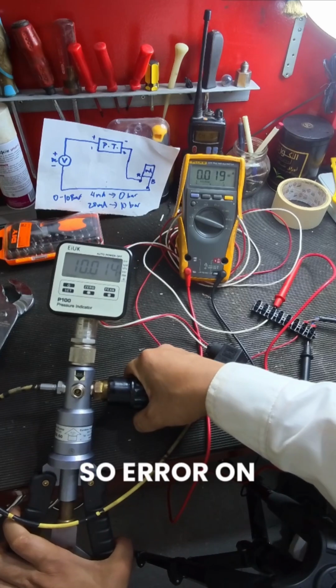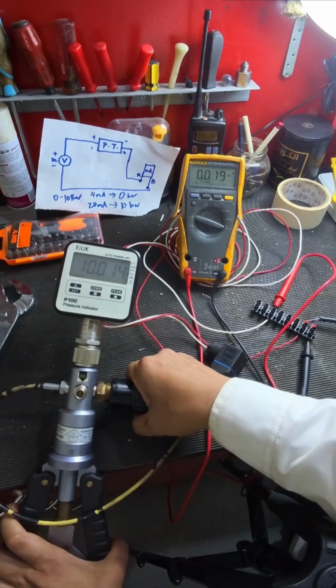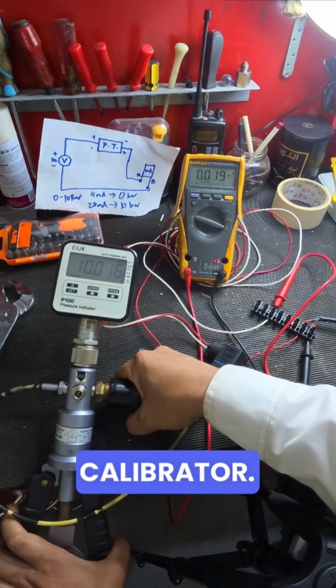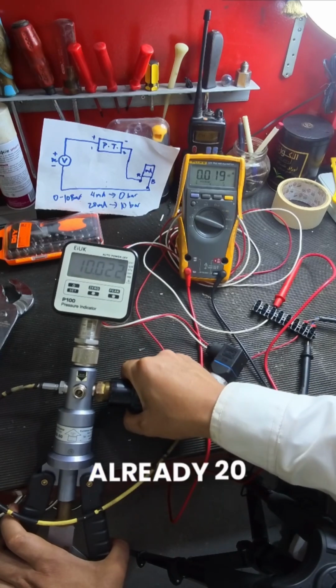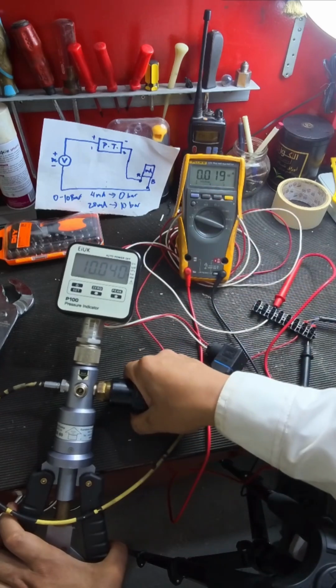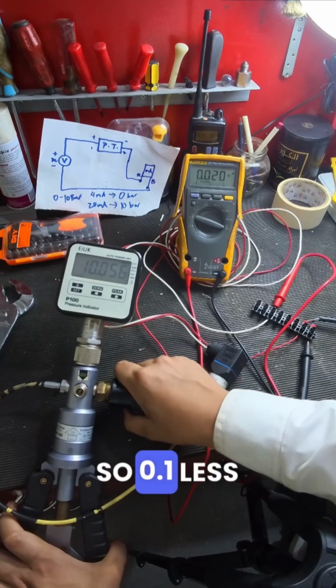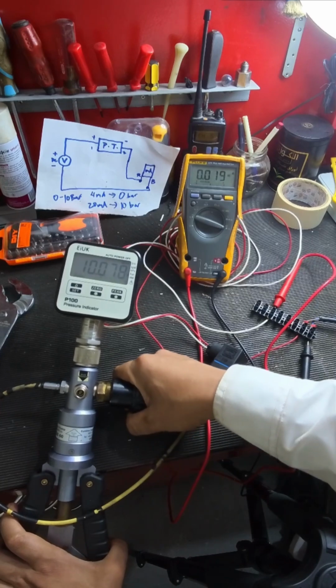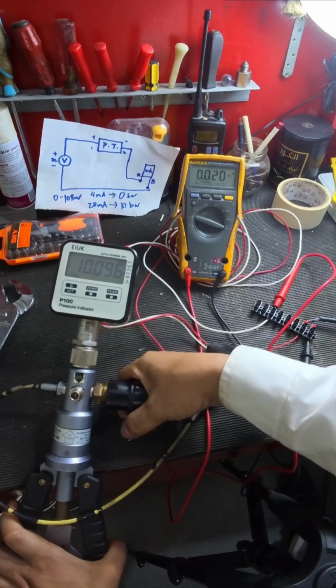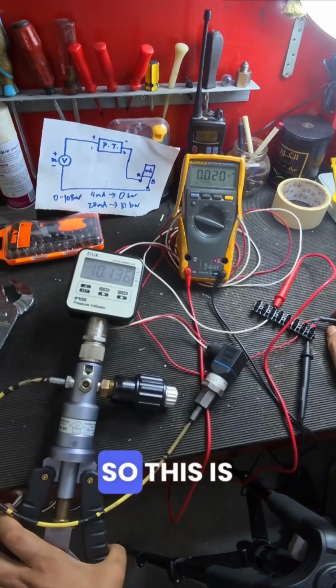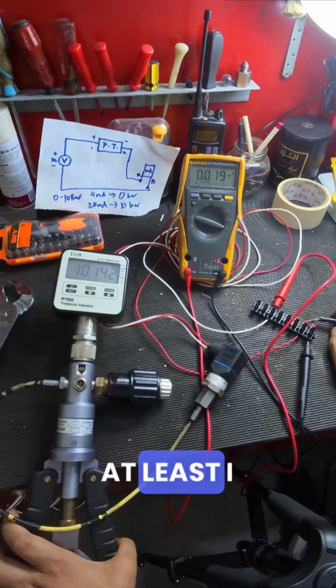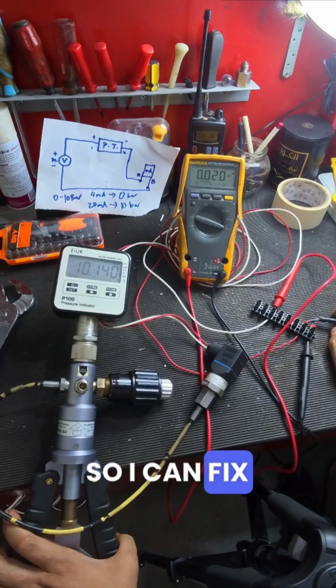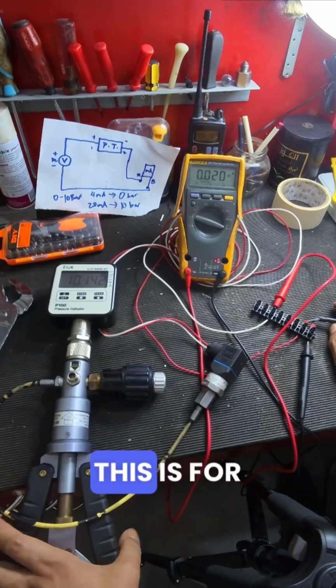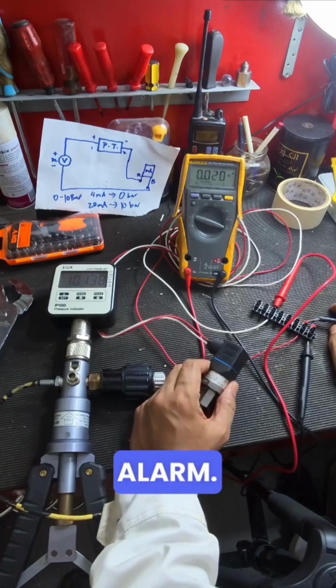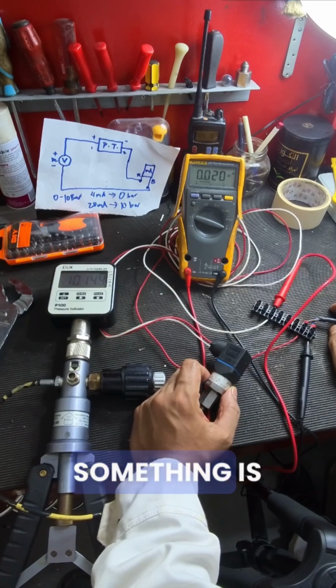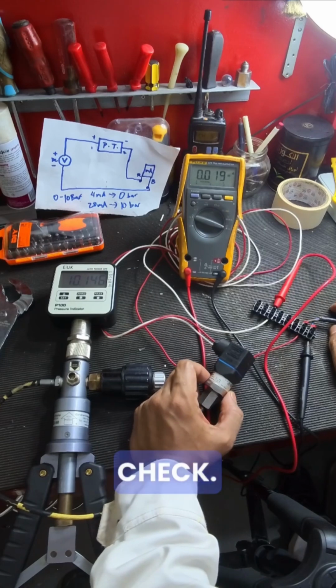It's almost accurate, guys. We don't have much error on the differential of this calibrator, but you see at 10 it already gives 20 milliamps. At 11.1 we get 1.2. So this is really good. At least I have one good spare, so I can fix my problem here, because this is for our ballast water treatment system. We always get an alarm that some PT is offline. So now I check, and now it's good.